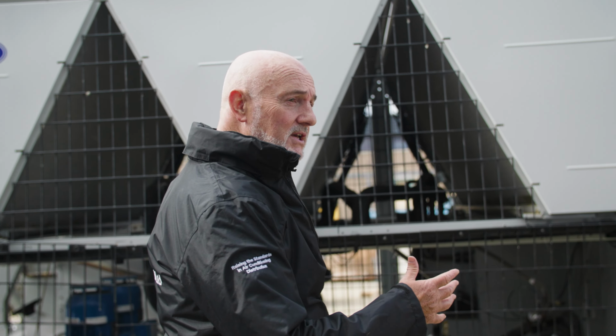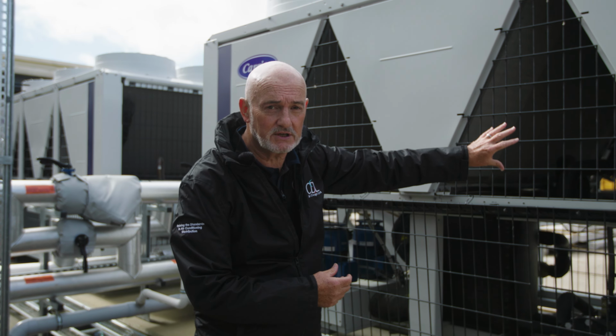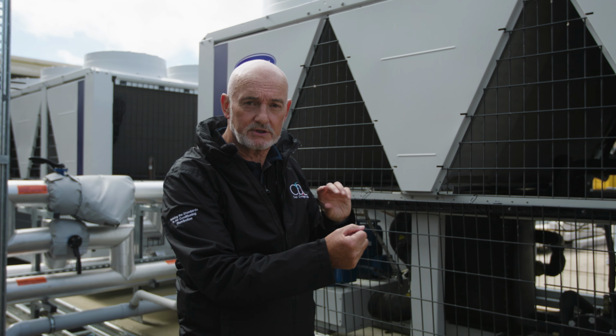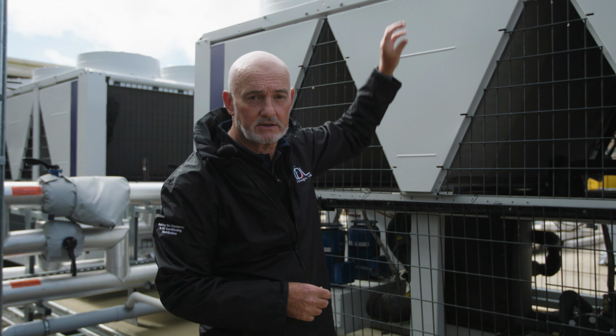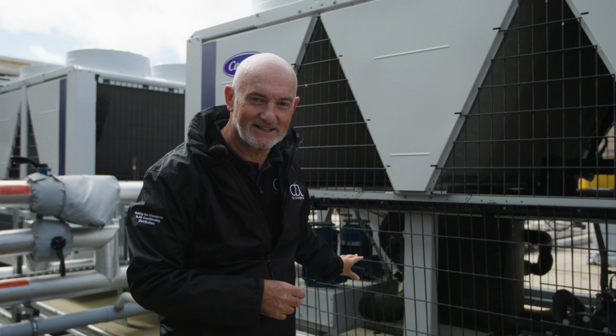Another component within this 30 RQP is that it's actually not just a heat pump. This particular product could also just be a chiller, giving cold water, for instance 6 and 12, if it was needed. In this particular application it's heating only, but you still get the reversing valve. The reversing valve is that multicolored brass thing within there, and it can change around such that these start to reject heat and put coldness into the heat exchanger.